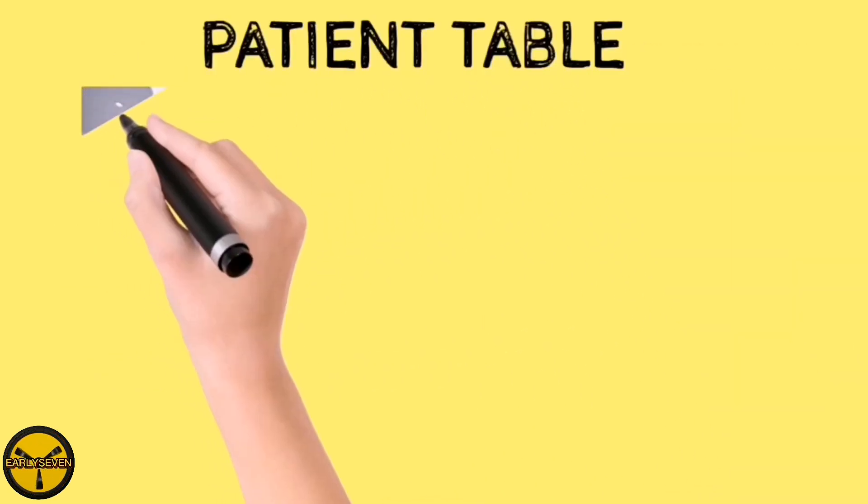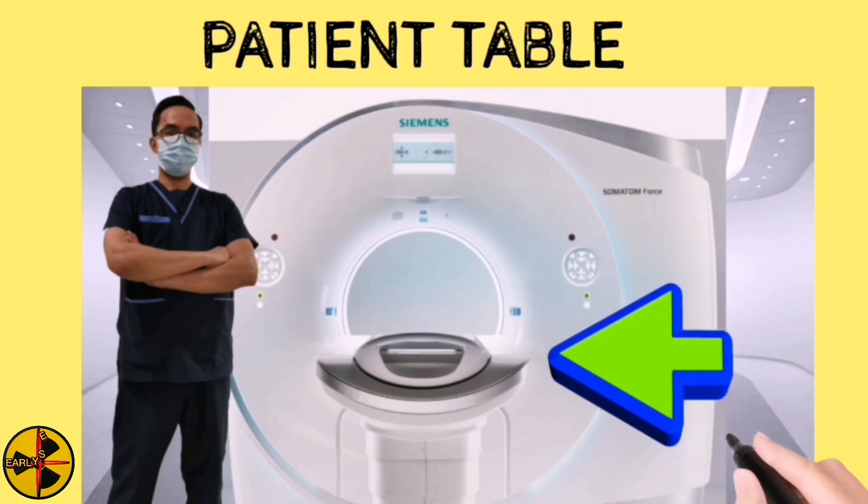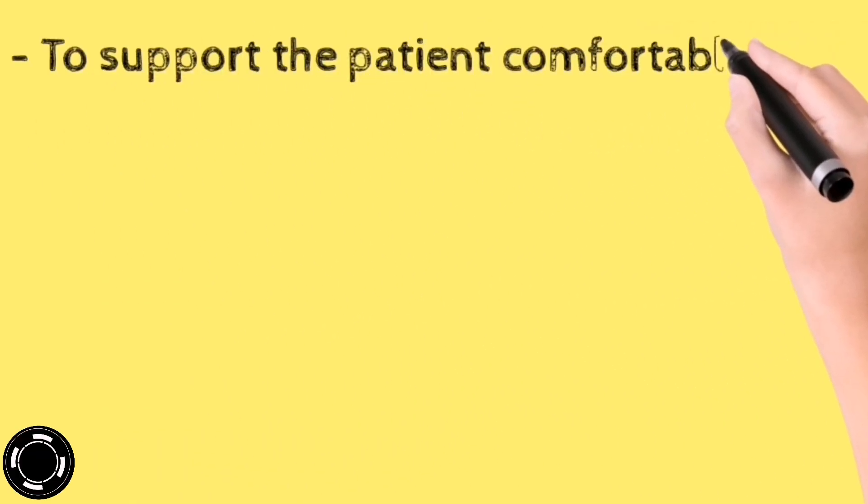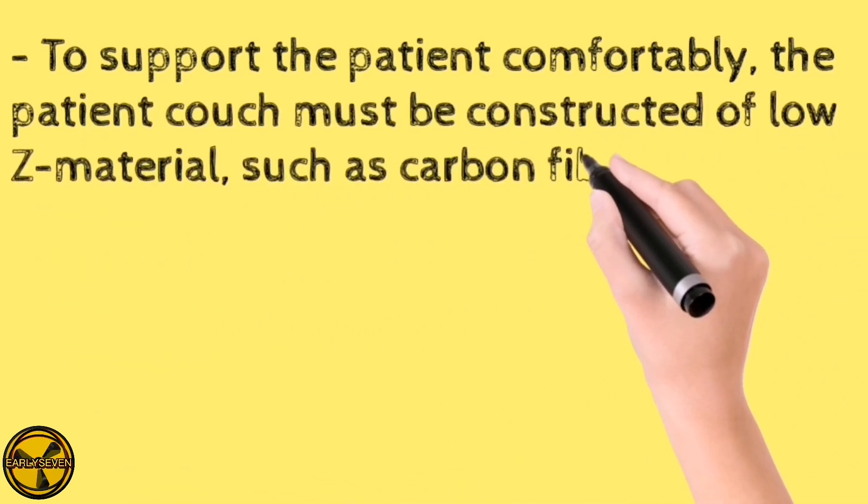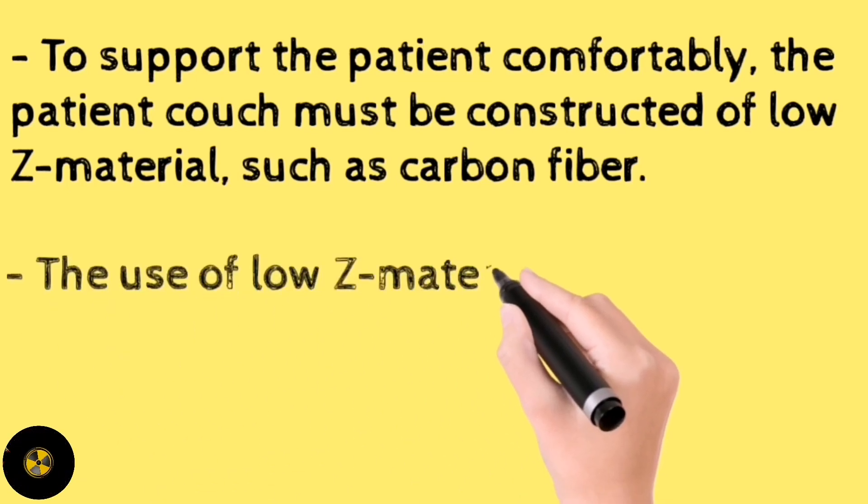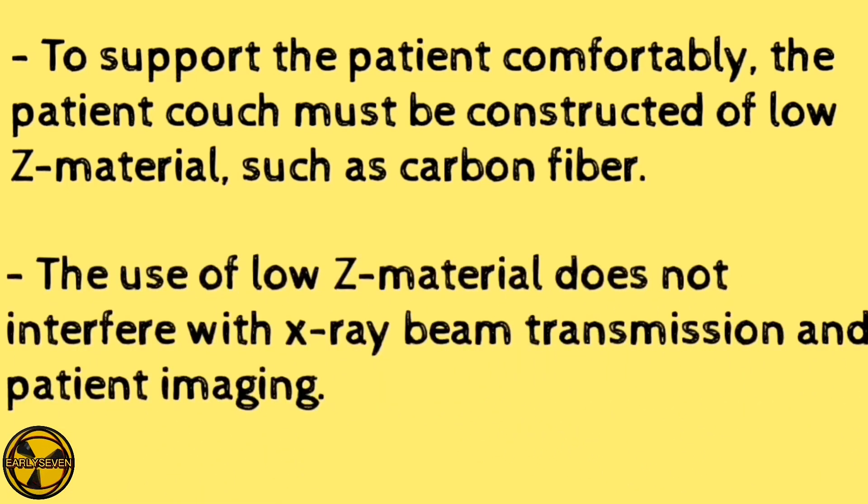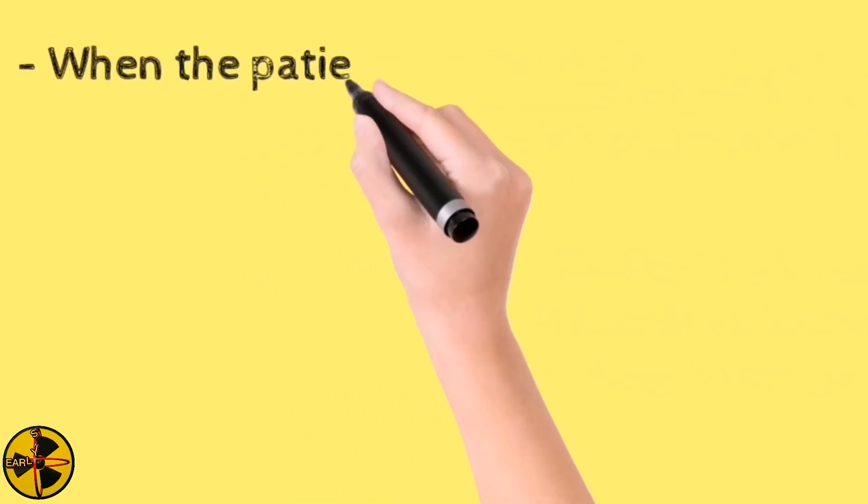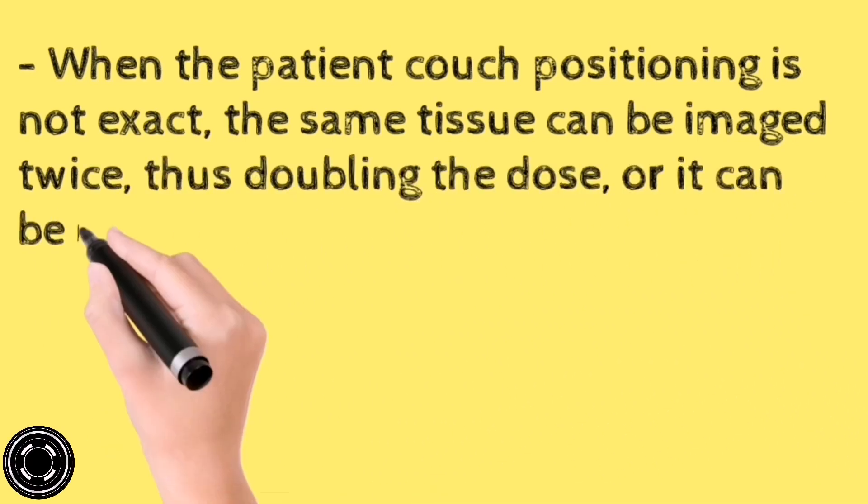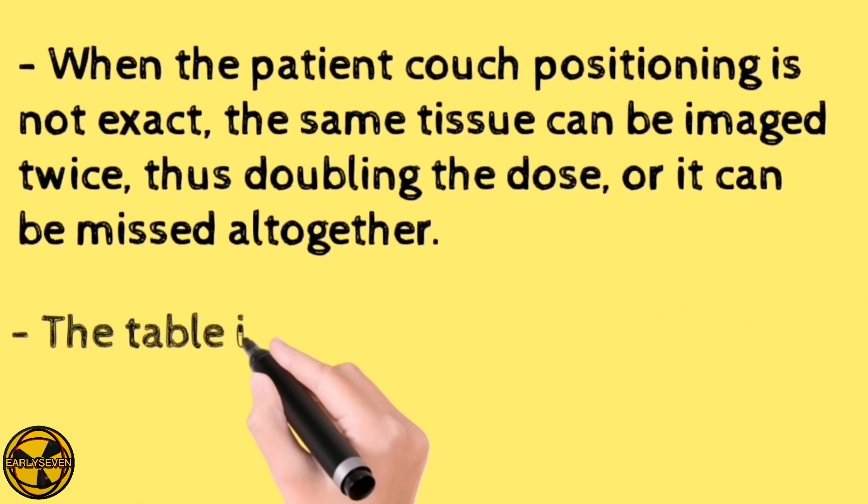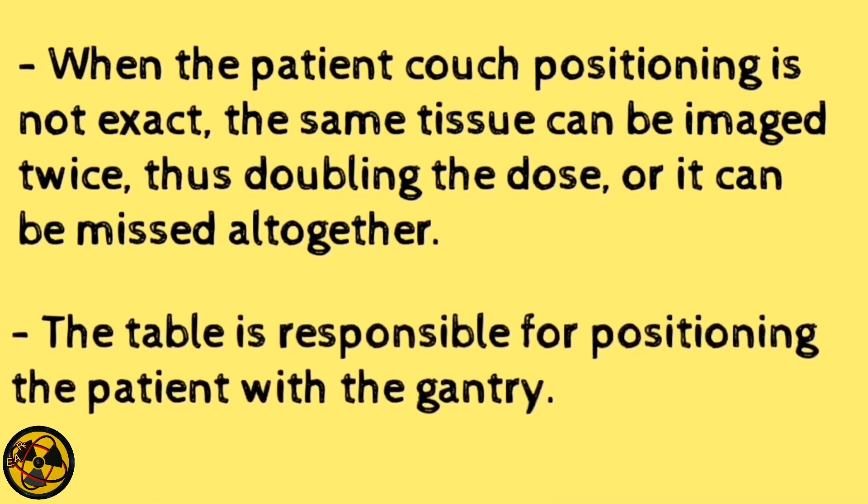Another component of a CT scanner is the patient's table. To support the patient comfortably, the patient couch must be constructed of low atomic material, such as carbon fiber. The use of low atomic material does not interfere with x-ray beam transmission and patient imaging. When the patient couch positioning is not exact, the same tissue can be imaged twice, thus doubling the dose, or it can be missed altogether. The table is responsible for positioning the patient with the gantry.